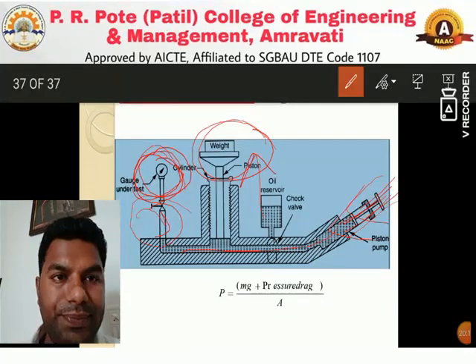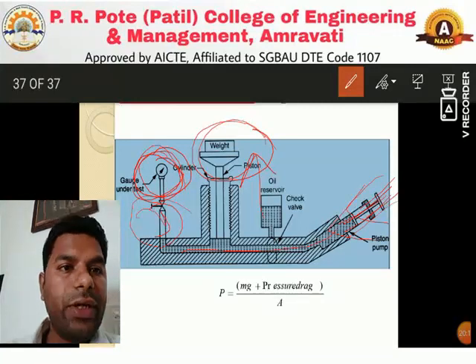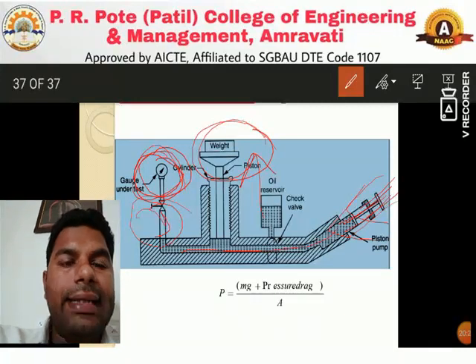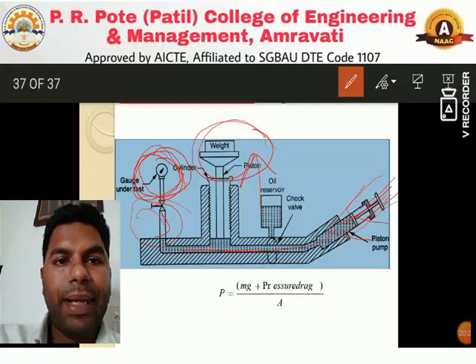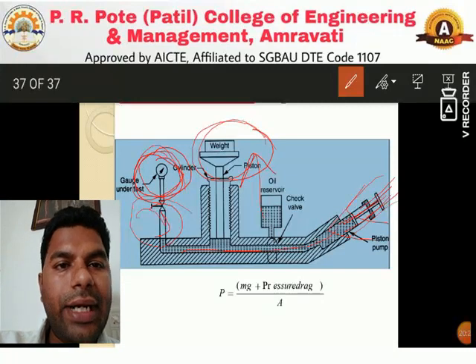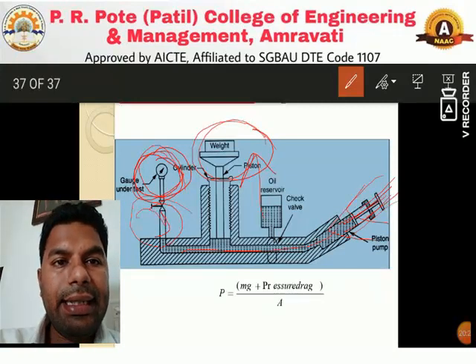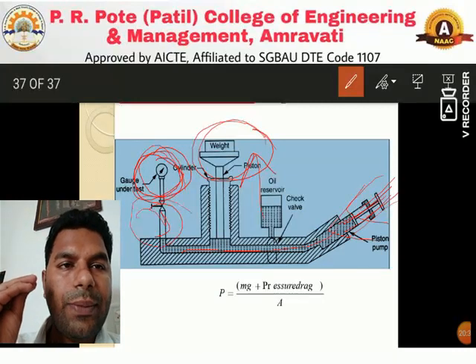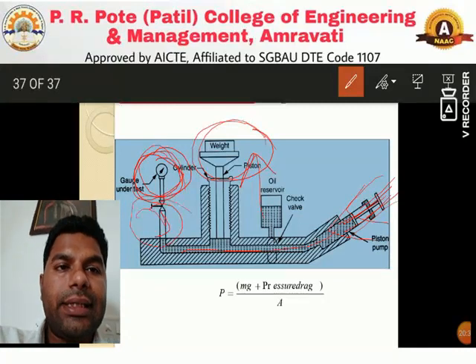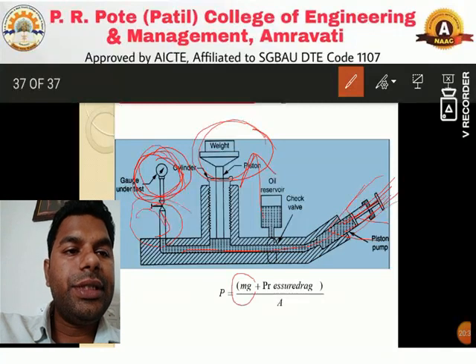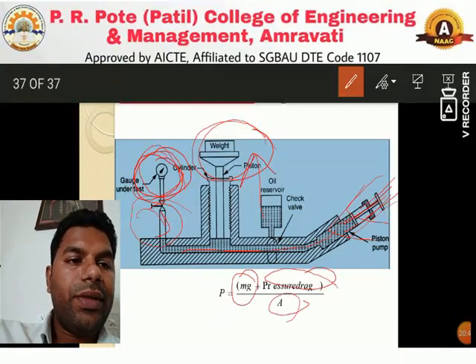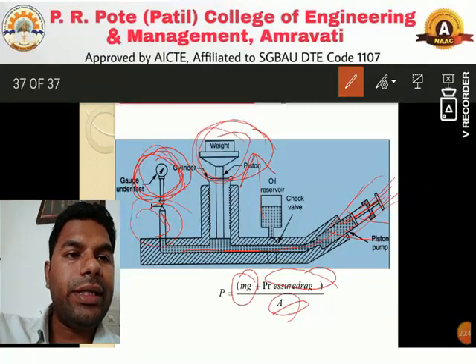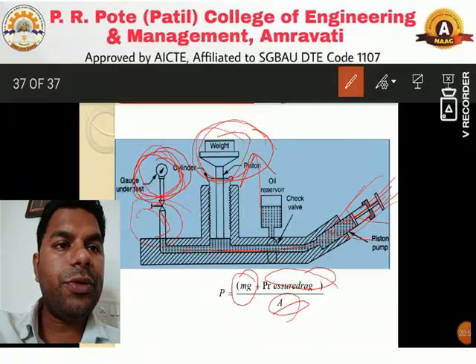Calibration is very important because without calibration we cannot use any device — we would not know what pressure corresponds to a particular reading. The dead weight pressure gauge is used to make this calibration. The formula used is: P = (mg + pressure drag) / area, where mg is the known weight force, pressure drag accounts for friction in the cylinder-piston model, and area is the piston area.